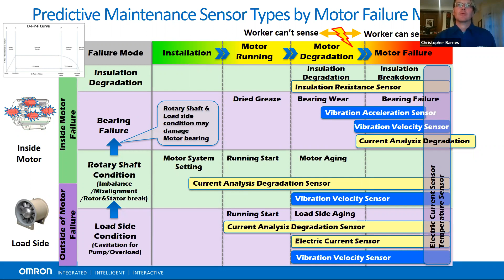If we look at the bearing failures, as the grease dries out and the bearing wear starts to happen, the vibration climbs up. We're going to be able to start picking it up first with vibration acceleration sensors, and then with current analysis as the resistance on the motor picks up. Similarly, for other conditions, we can pick it up with the sensors. Some, such as current analysis, will pick things up earlier than vibration, whereas bearing failure gets picked up by vibration first. So it's nice to have a couple of different sensors that give you clues as to what's going on, because the sensors can't tell you what's going wrong, but they'll tell you that something's going wrong. And as a human, you need to interpret the data to see what's happening.